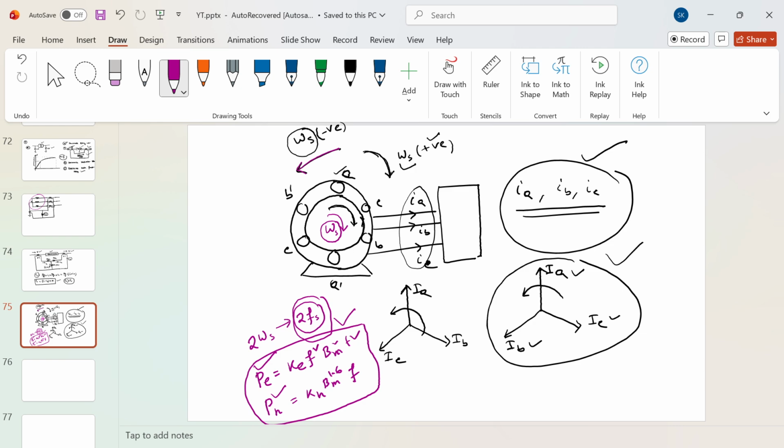So there will be much more core loss in the alternator or synchronous machine, and that can lead to overheating. To reduce this phenomenon, or to completely eliminate it, we use the negative sequence relay. In the negative sequence relay, the actuating quantity is basically the negative sequence component.